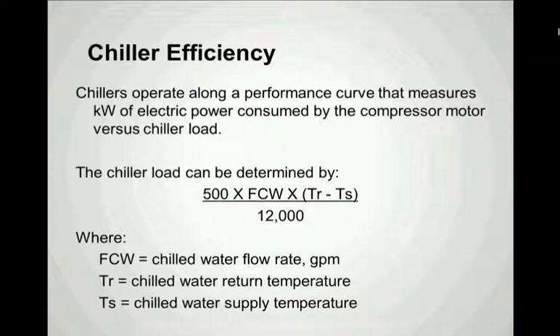We can estimate the chiller load based on this simple equation where we're looking at the chilled water flow rate in gallons per minute. This is the water that's flowing through the evaporator section of the chiller. So we're looking at the chilled water flow rate, gallons per minute, times the temperature differential, the return and supply temperature of the chilled water. And if we do the calculation, we arrive at the tons of load carried by that chiller based on temperature differential and flow rate of the chilled water. The 12,000 is just a conversion factor that says there are 12,000 BTUs per ton of cooling. So this tells us our chiller output.